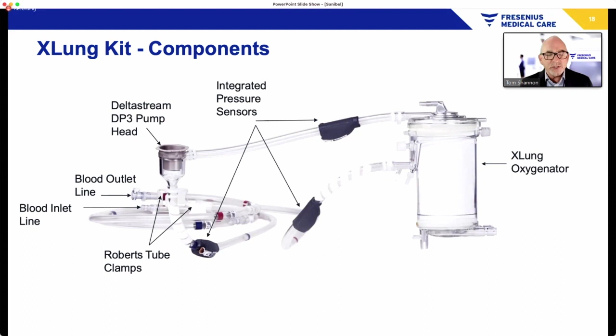The X-Lung oxygenator is a 1.9 meter squared oxygenator, and our Delta Stream DP3 pump is a 17 ml prime pump. I'll quickly go through those. The circuit is rated up to 7 liters, and the entire circuit's a little over 600 mLs in prime. Again, a 1.9 meter squared PMP oxygenator.